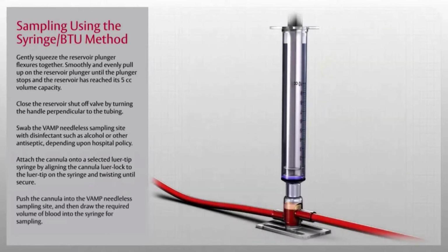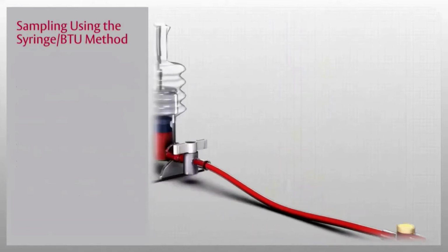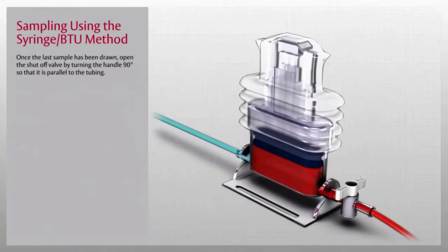Push the cannula into the VAMP needleless sampling site and then draw the required volume of blood into the syringe for sampling. Note: do not use a hypodermic needle through the sampling site. To remove the syringe cannula assembly from the sampling site, grasp the cannula and pull it straight out. Once the last sample has been drawn, open the shutoff valve by turning the handle 90 degrees so that it is parallel to the tubing.